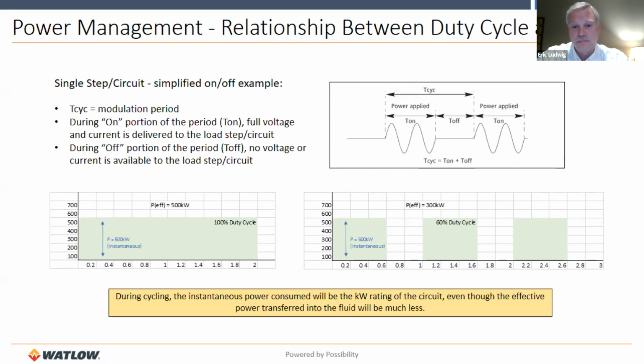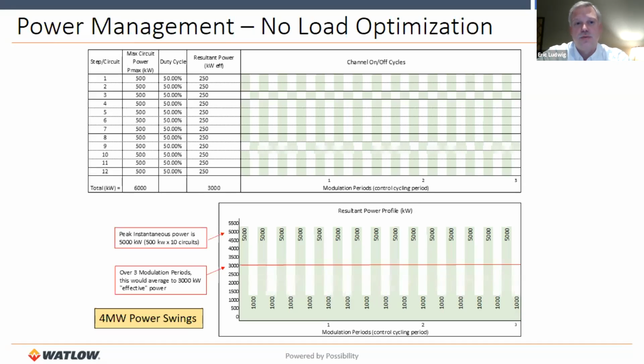Next slide, please, Dennis. If we have a 12 circuit heating system, each one of those circuits 500 kilowatts, and we're firing those circuits 50% of the time, and we have no coordination with those circuits. Each one is allowed to run its own control loop independently and fire on and off independently. What you see by the green and white checkerboard pattern in the top graph is the on-off cycles. Every time it's green, that particular circuit's on. Every time it's white, that particular circuit's off. So I'm using a 1 second modulation period, and I'm showing you 3 cycle periods here.